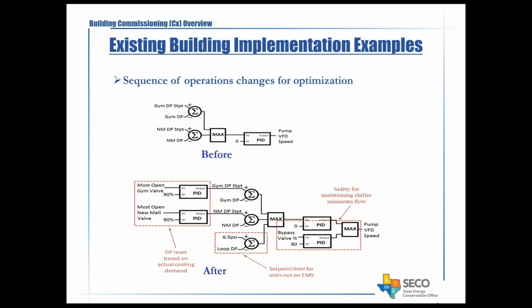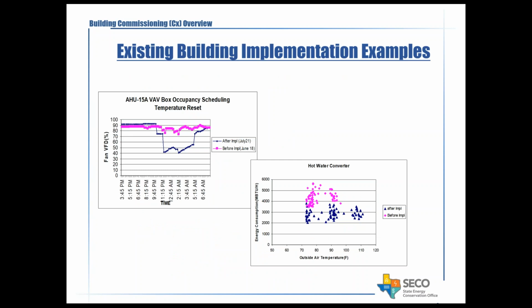It's important that the controls are well understood by the commissioning agent. This is an example of a project we were involved in which there was a sequence modification. The sequence above is what they had before - basically a constant DP set point that the chiller was controlled at. A review and modification of the existing control sequence was done primarily to optimize operation for energy savings and also build in some safety factors. So controls are an important aspect in existing building commissioning, and we need to be aware of that.